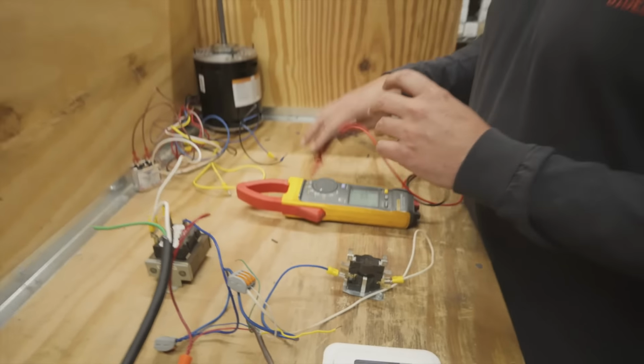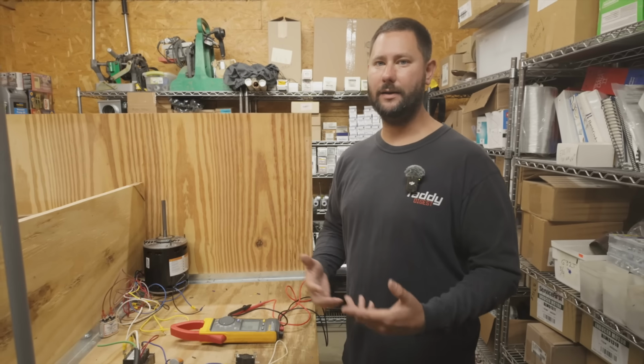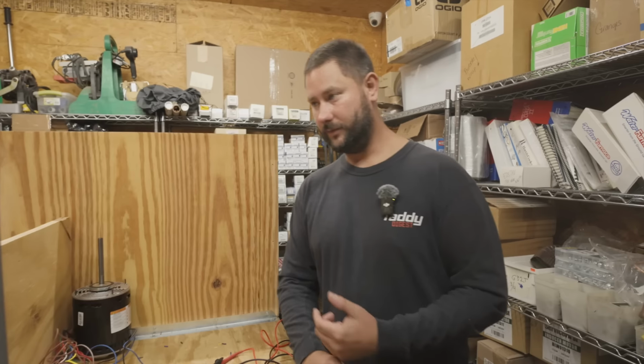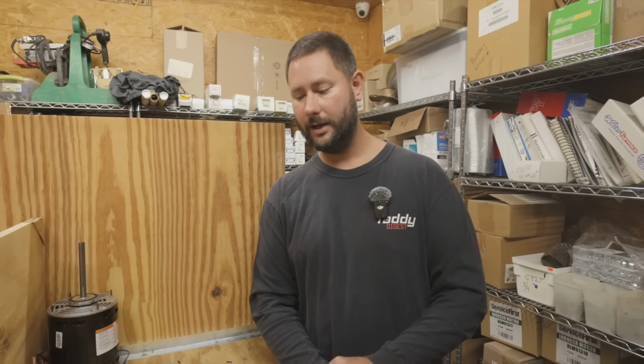So why would this sequencer, why would this relay have a delay? Well, if it's in a mobile home and it's using a heater kit, you might want your fan motor to kick on before your heater kit kicks on. What happens if your heater kit kicks on before your fan? You've got a limit switch, it's probably going to overheat. It's going to open the circuit. So having the heater kit kick on after the fan motor is already started is a good idea.